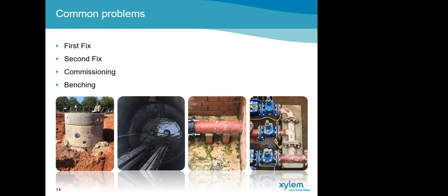If the wet well is core drilled for the interconnecting pipe work, this must be in line and not on the perpendicular to the circumference. What that means is if you're on the perpendicular, as you've got the pipe work going through, you've got less of a clearance between our pipe work and the circumference. In the past, it used to be a letterbox arrangement. However, I've noticed recently that water authorities are asking for this to be core drilled again.